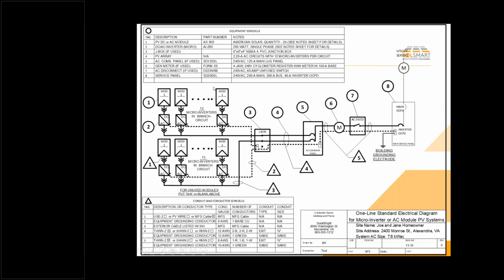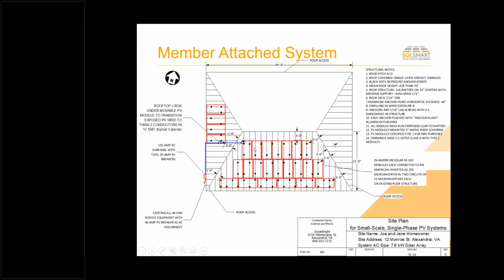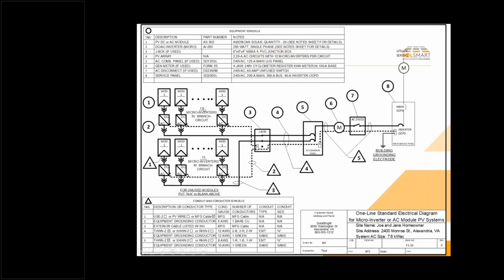Okay. So now we're looking at the diagram. We can see it's quite a bit different from the standard diagram for the microinverters, and it tells us we should have 13 and 13 in this, since we said we had 26. I'd have to go back and count all the modules on the roof, and so that would be part of my checking job. I got 4 here. I've got 2, 4, 6, 8, 10, 12, 14, 16, 18, 20, 22, 24, 26. So 26 is the right number, and I'd have to go back here and say, oh, this has got to change to 13, and we're good to go. It has all the details about the equipment and the disconnecting means requirement. We have a little AC combiner panel where we combine the circuits together.